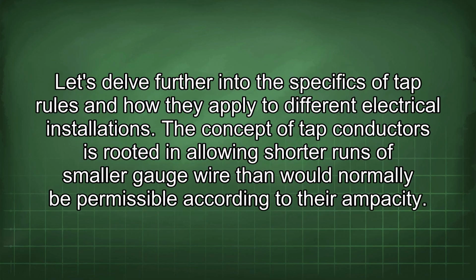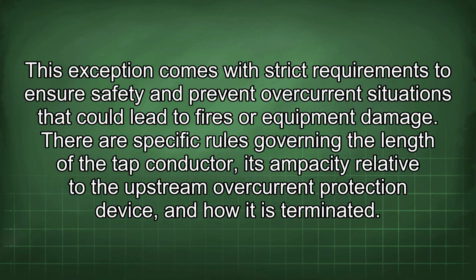Let's delve further into the specifics of tap rules and how they apply to different electrical installations. The concept of tap conductors is rooted in allowing shorter runs of smaller gauge wire than would normally be permissible according to their ampacity. This exception comes with strict requirements to ensure safety and prevent overcurrent situations that could lead to fires or equipment damage. There are specific rules governing the length of the tap conductor, its ampacity relative to the upstream overcurrent protection device, and how it is terminated.